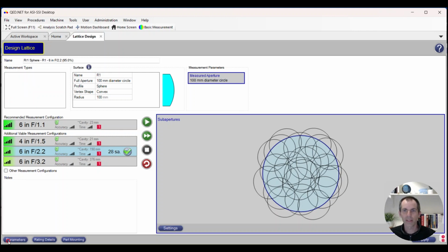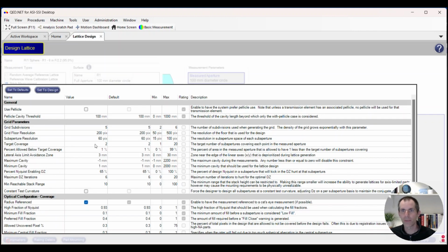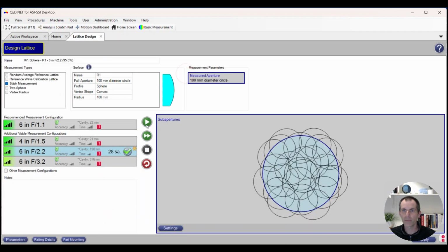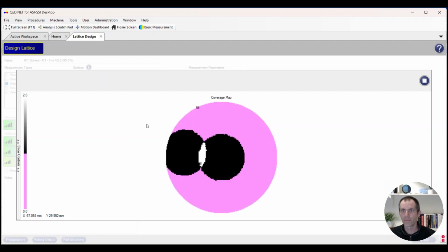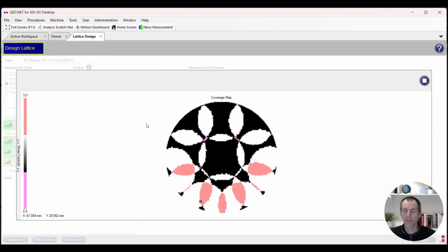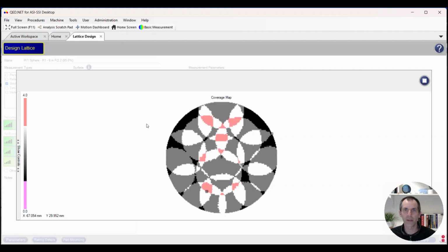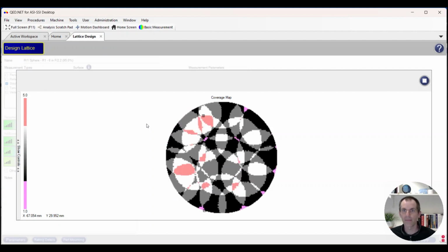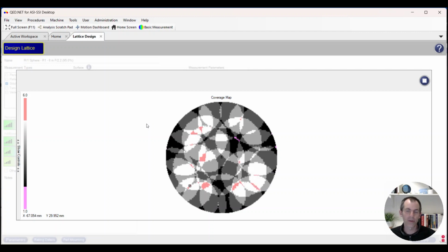So now if I go back to the parameter screen, it's just a matter of increasing this from 2 to say 3, where we want each point on the surface to be measured by at least 3 subapertures. So I'm going to click off and redesign the lattice.